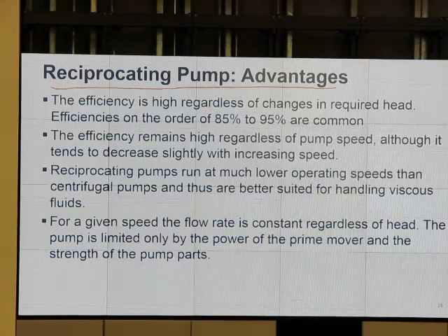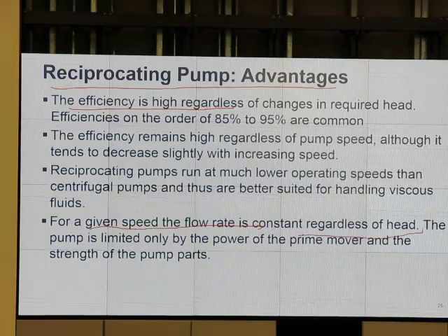Reciprocating pump. The advantage is very high efficiency because we push directly. That's the main point, and it gives the same flow rate regardless of the head. So regardless of how much the pressure pushes against the pump, it delivers the same flow rate. It doesn't deliver more or less. So it's not sensitive to viscosity. When viscosity goes up, PD delivers almost the same.